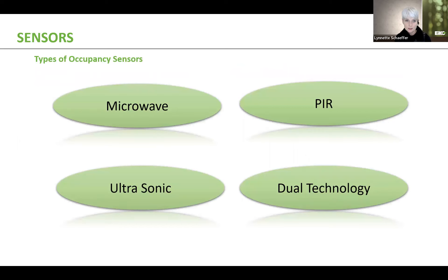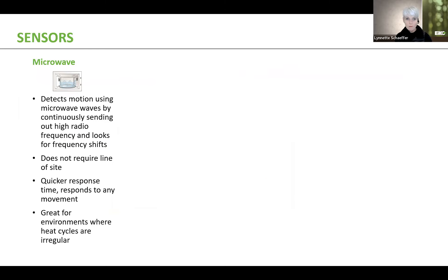Now there are four types of occupancy sensors. There's microwave, PIR, ultrasonic, and dual technology. Microwave basically just detects motion using microwaves by continuously sending out kind of like these radio frequencies. And it looks for any frequency shifts. So it does not require line of sight. It's not like the matrix where you have lines of sight coming out, you know, red lines. It is actually just looking for a shift in the frequency. Microwave sensors are great because they have a quicker response time. It responds to any form of movement. Keep that in mind. It's great for environments where heat cycles are also irregular because it's not looking at any type of heat in the space.